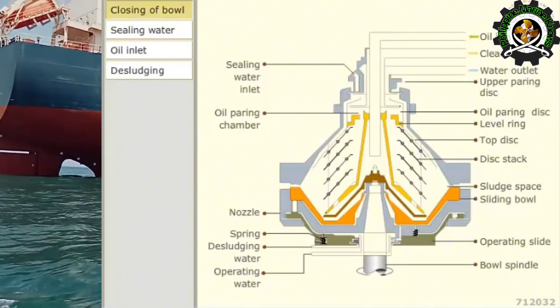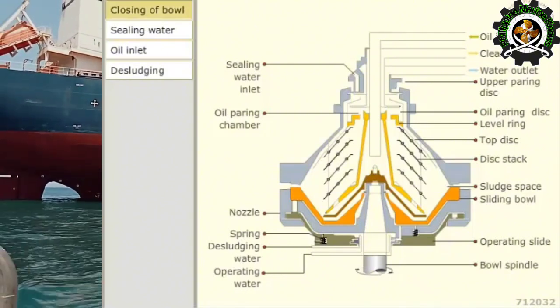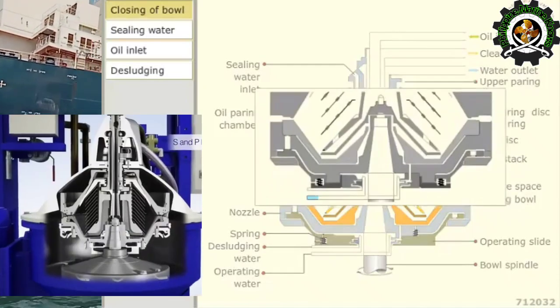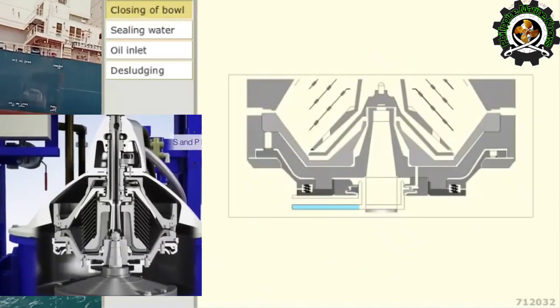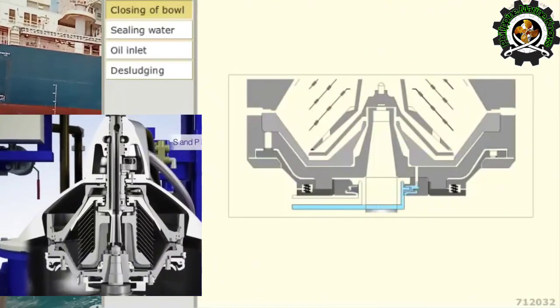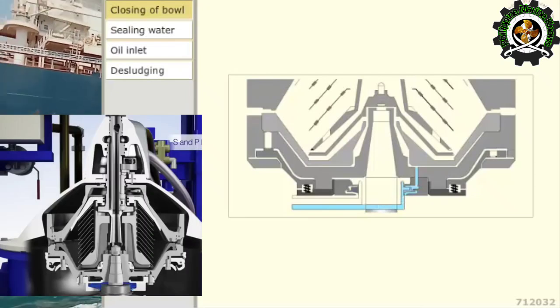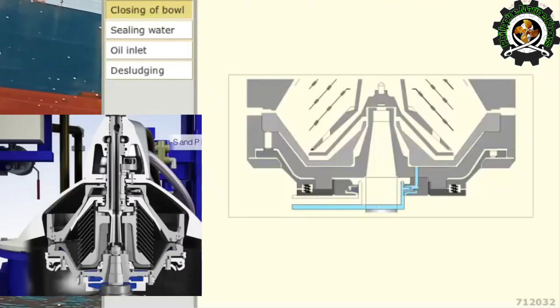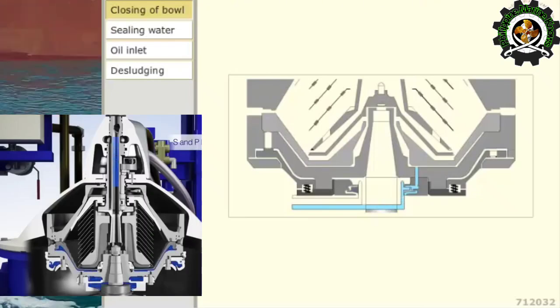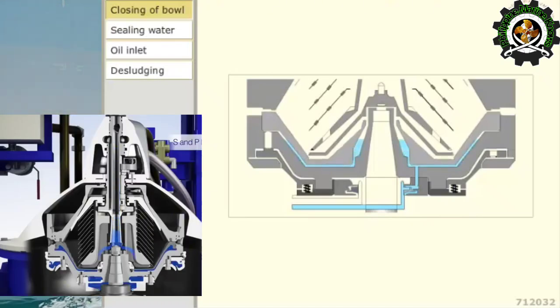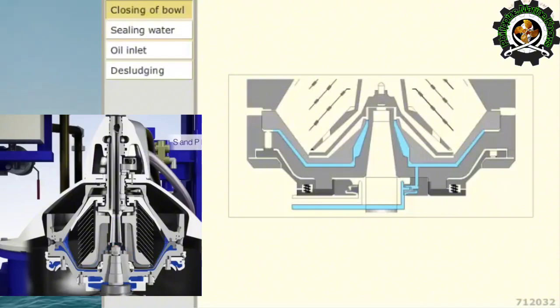After the purifier has attained its full rpm, the bowl closing water, also called the operating water, is supplied at the bottom. The sliding bowl bottom is pressed upwards against a seal ring by the hydraulic force of the operating water.